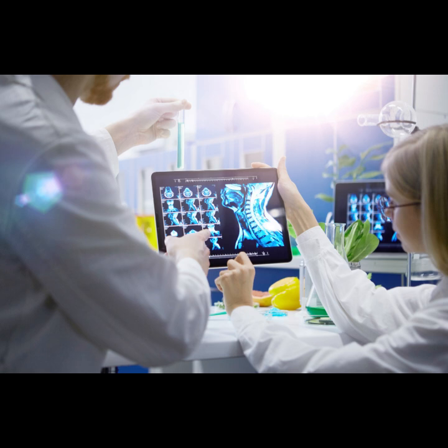Then we slide the patient into the scanner, into that huge tube. That's the main magnetic field, the B0. That's the big one. B0 in hospitals is typically 1.5 Tesla, maybe 3 Tesla. Research systems push it way higher, though. We're talking up to 9.4 Tesla for human imaging now. Wow. That's powerful. The sheer power of B0 is immense.